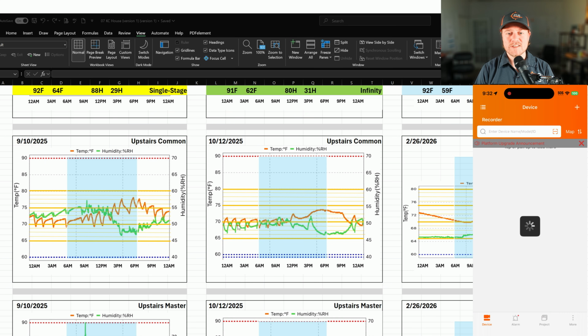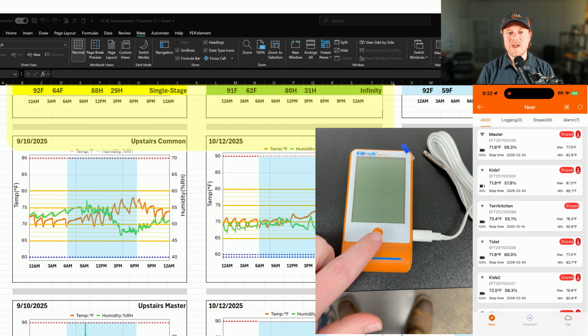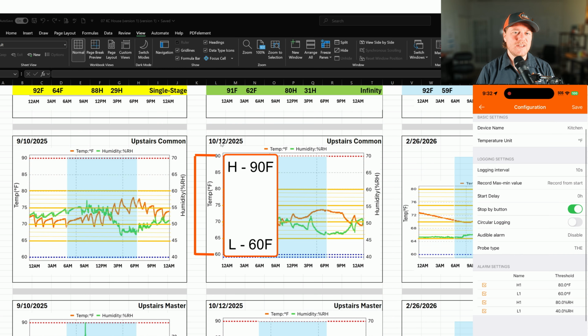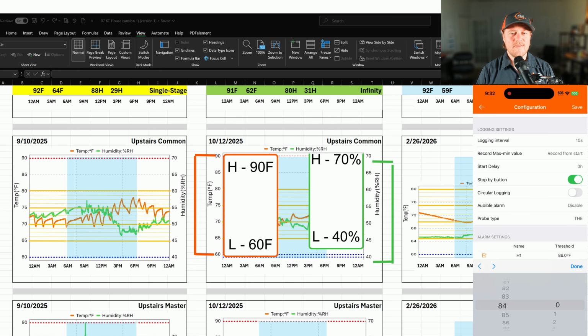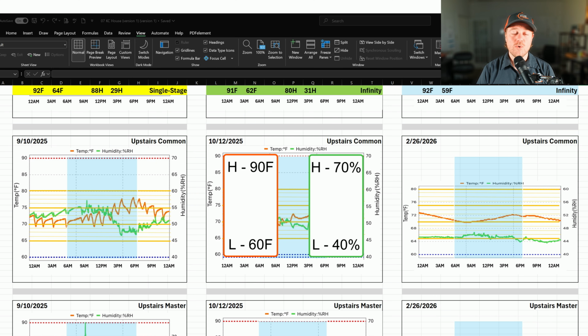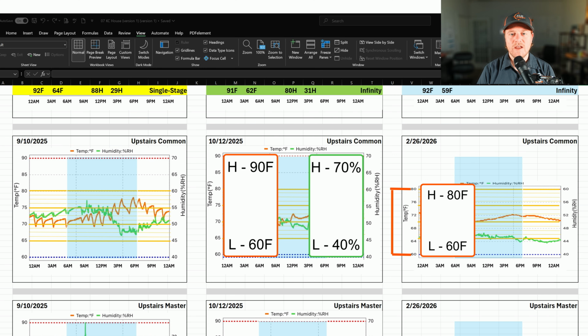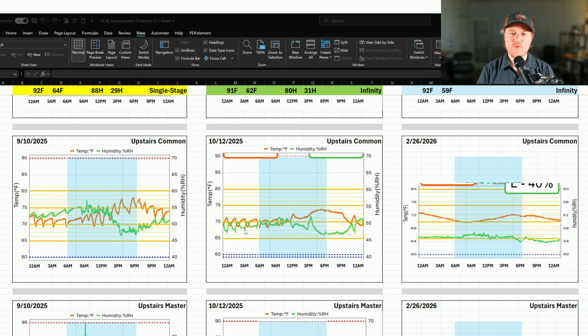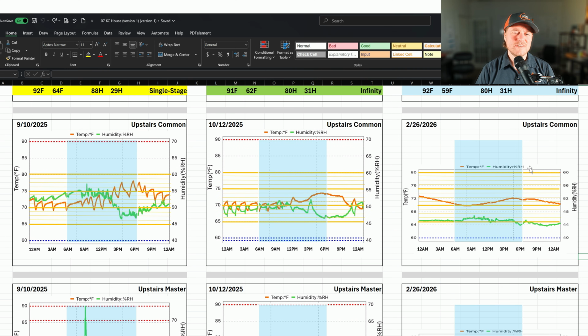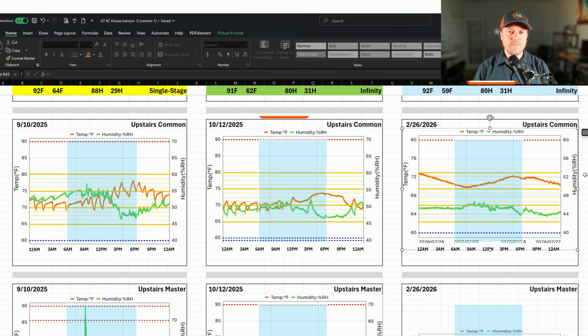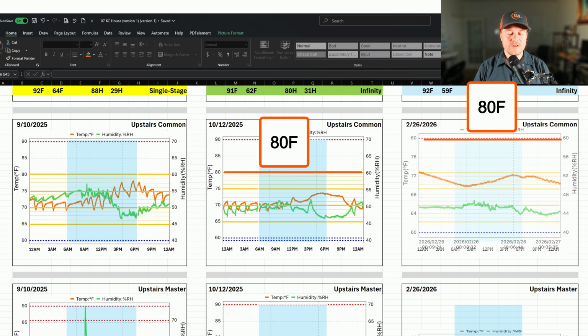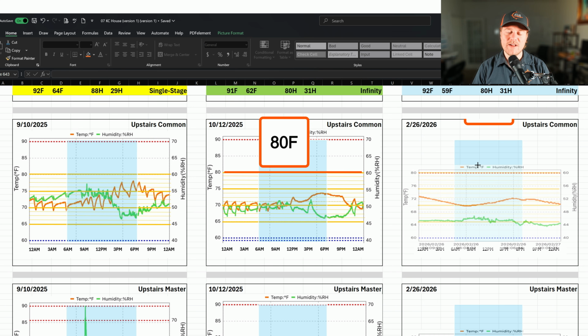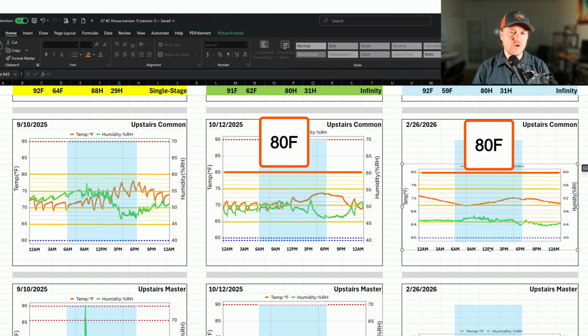Before we get started, I have to make a couple disclaimers. On the earlier data log reports before we changed out the ductwork, I had the temperature range set between 90 and 60 degrees Fahrenheit and 70 and 40% humidity. On the newer readings, I had the temperature set between 80 and 60 degrees Fahrenheit and the humidity between 60 and 40%. And what that's doing, it's making these graphs look like this. Now the temperatures are no longer aligned, and by crunching the graph down, now everything aligns correctly. So if you're wondering why the newer graphs look a little bit different, that's the reason why.